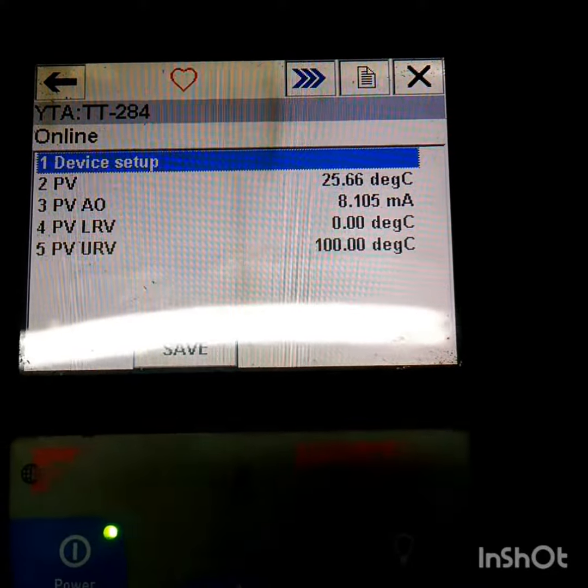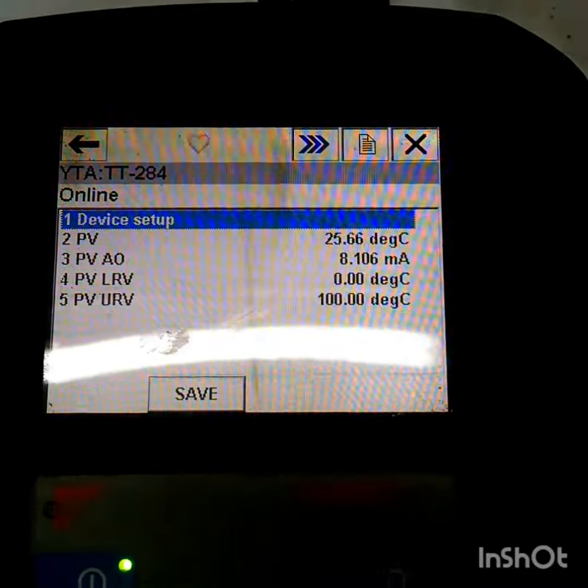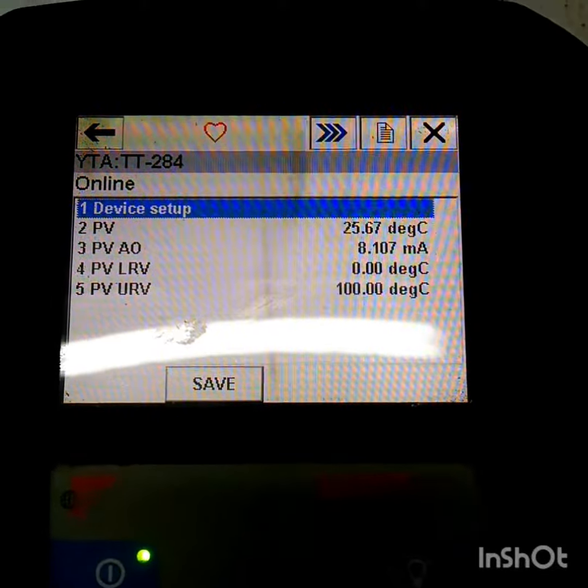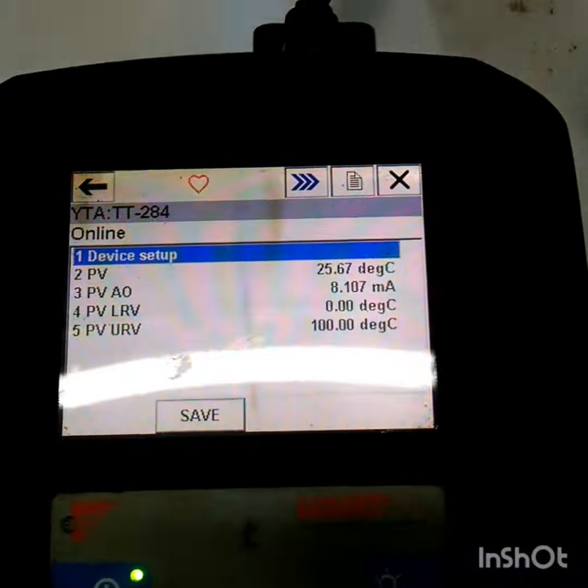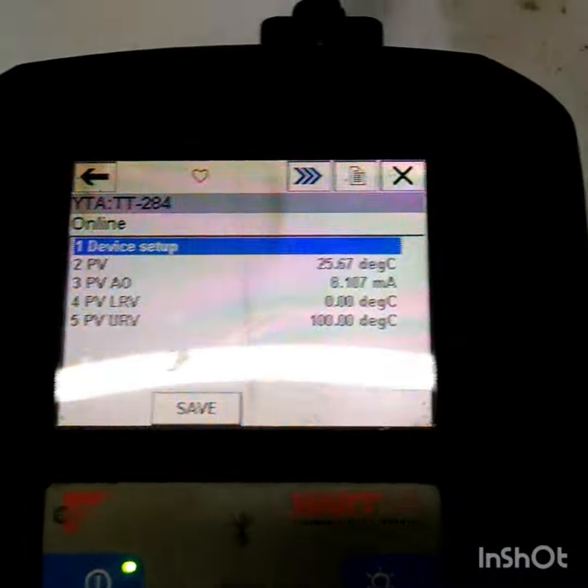That's why we use the three-wire loop — to reduce and compensate the loop wire resistance. If the transmitter and the RTD are close together, there's no problem and we don't need a three-wire.